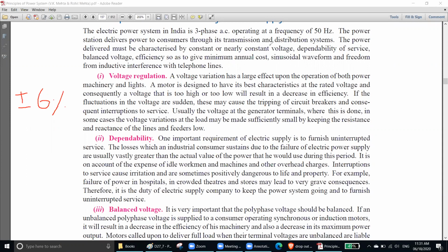A voltage variation has a large effect upon the operation of both machinery and lights. Your power machinery and lights are affected if your voltage goes up or down. A motor is designed to have its best characteristics at the rated, constant voltage. Consequently, a voltage that is too high or too low will result in decreased efficiency—your motor will lose efficiency if the voltage is bigger or smaller than rated.